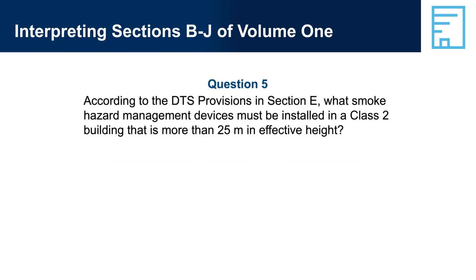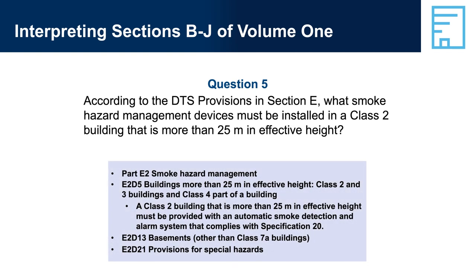Question 5: According to the DTS provisions in Section E, what smoke hazard management devices must be installed in a Class 2 building that is more than 25 metres in effective height? Part E2, smoke hazard management; E2D5, buildings more than 25 metres in effective height — Class 2 and 3 buildings and Class 4 parts of buildings. A Class 2 building that is more than 25 metres in effective height must be provided with an automatic smoke detection and alarm system that complies with Specification 20. E2-D13 basements (other than Class 7A buildings) have similar requirements as per E2-D5. E2-D21 provisions for special hazards: additional smoke hazard measures may be required if the building has special characteristics, functions, materials, or mix of building classifications. The relevant authorities will advise on whether this provision will be applied to a building.